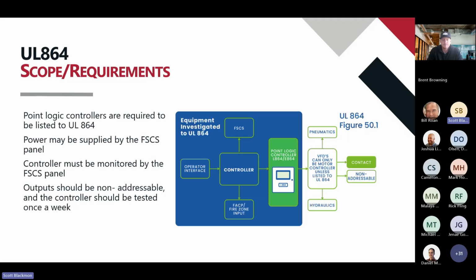Now, what we've seen in the past is contractors and controllers take a system. They will say, hey, we'll take this VFD. We're going to add a couple of pressure sensors to it. We'll write a program for the VFD. The VFD will modulate up and down according to pressure. Well, what they've done is they've turned that VFD into a point logic controller. And so now that VFD and that program, by UL and IBC, need to be listed to UL 864. So they need to call a listing agency out to come and test that system and certify that it works and works correctly.